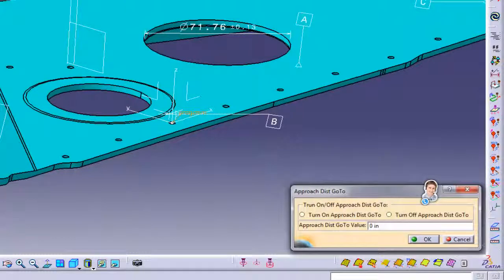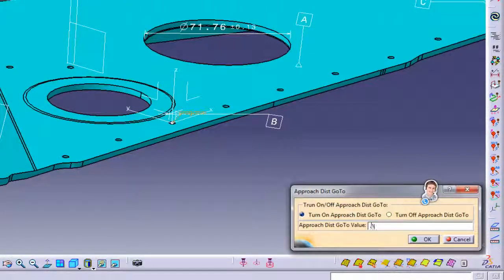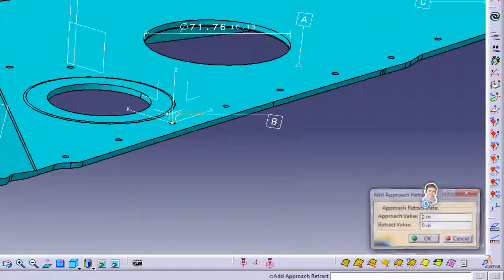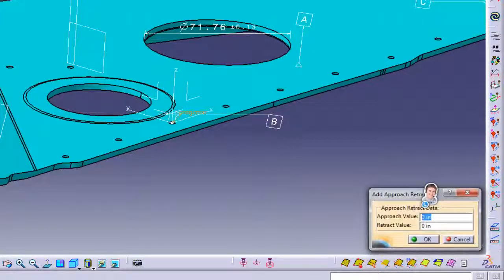They can then define the probe approach and retract go-to moves. This will guide the probe moves before and after each feature measurement. They can also define the probe approach and retract distance.